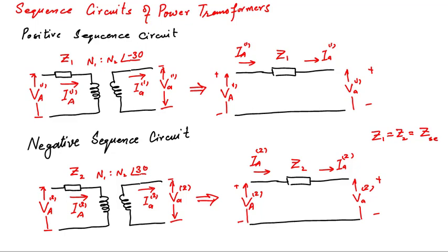When we say there is a phase shift in delta Y transformer and high side quantities lead the low side quantity by 30 degree according to IEEE standard, that definition was actually for positive sequence. When we are discussing the balanced system, there is only one sequence that is present over there, and that is positive sequence. But here when our currents and voltage will become unbalanced, then negative sequence and zero sequence get also involved. Now here the definition of phase shift is more detailed.